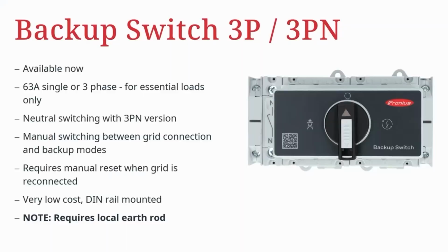However, if you have a 100 amp incoming supply, we'd recommend breaking out the non-essential loads, those high loads such as an oven, an EV charger, and then only backing up the essential devices that you need to operate during a grid failure. Of course, this needs a manual switching between the grid mode and the backup mode, but it is a very low cost and simple solution.